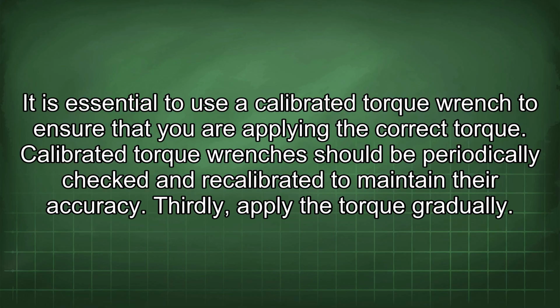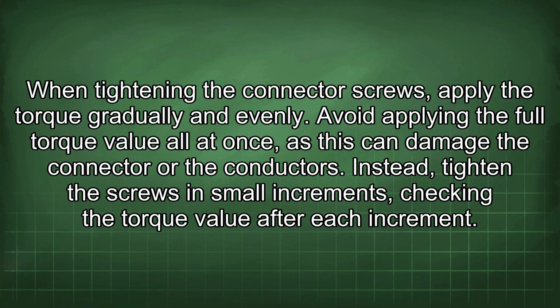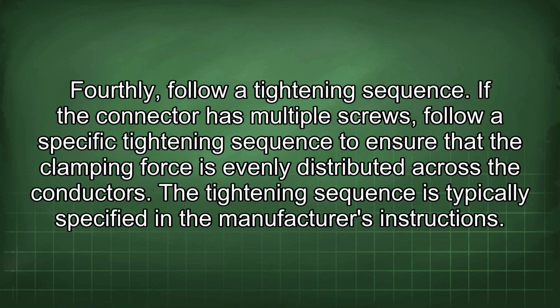Thirdly, apply the torque gradually. When tightening the connector screws, apply the torque gradually and evenly. Avoid applying the full torque value all at once, as this can damage the connector or the conductors. Instead, tighten the screws in small increments, checking the torque value after each increment. Fourthly, follow a tightening sequence. If the connector has multiple screws, follow a specific tightening sequence to ensure that the clamping force is evenly distributed across the conductors. The tightening sequence is typically specified in the manufacturer's instructions.